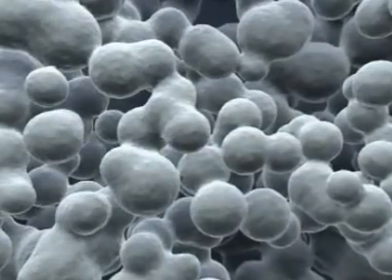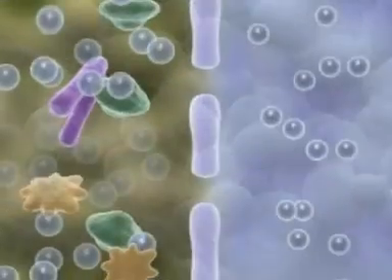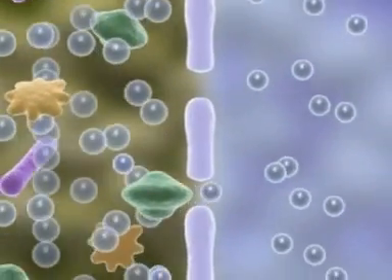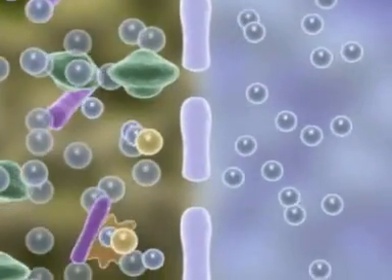These panels incorporate a rigid plastic frame as support, with ultrasonically welded membrane sheets on either side. The membrane material is a chemically stable polymeric sheet and is manufactured with a nominal pore size of 0.4 microns. In operation, a dynamic layer of protein and cellular material covers the membrane. This minimizes the pore size, producing an effective ultrafiltration range. Results show this membrane process significantly reduces bacteria, parasites and viruses.